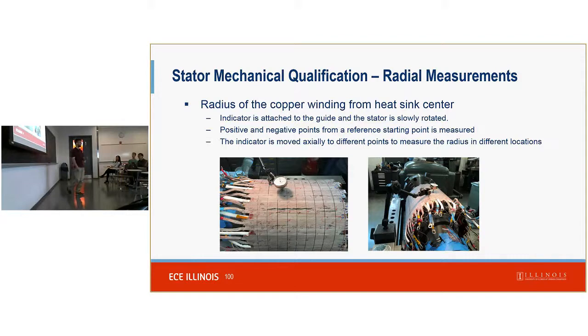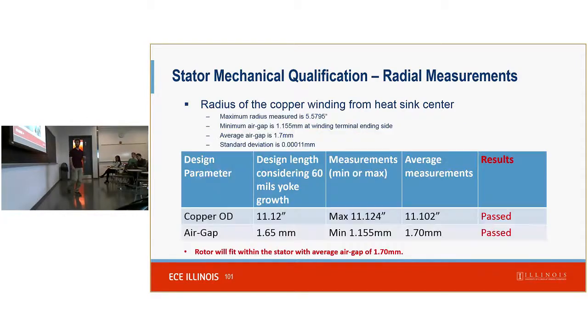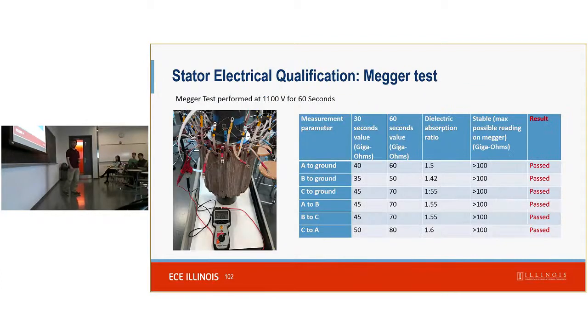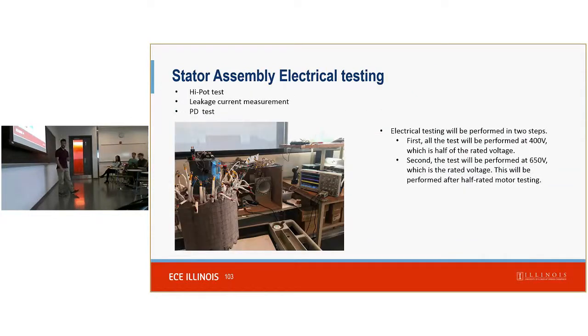And next, talking about the qualification, how we made sure that mechanically and electrically, I've already discussed electrically somewhat, this was the right size. So we measured the outside radius of the stator, and found that it was within an acceptable tolerance of the nominal value. And based on that, it looks like the average air gap will be about 1.7 millimeters, which is acceptable. It's about where we want it. Again, we retested the insulation and found that, again, it was acceptable and high enough for what we were looking for.